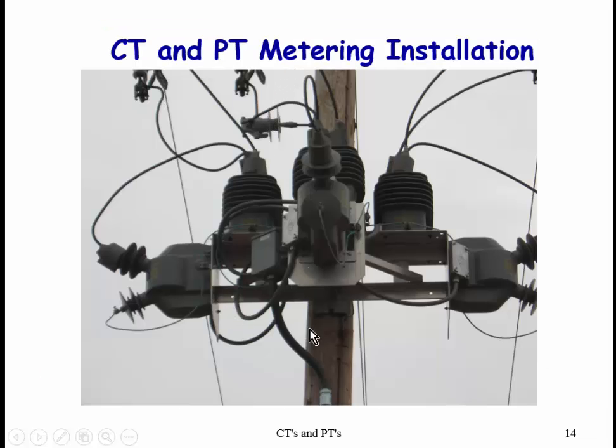So now this looks like guts on a fence, but this would be an installation. This was taken kind of out near Rosette, where CTs and PTs are installed together, with no regard for making this look good. If you look really, really close, you can kind of figure out what's what. But this is a potential transformer, and so is this, and so is this. If you look really close, the potential transformers are 120 to 1. Now these are the CTs, and they look like they're 200 to 5.